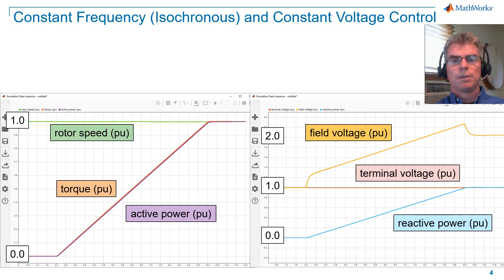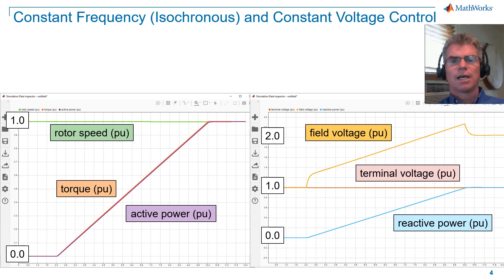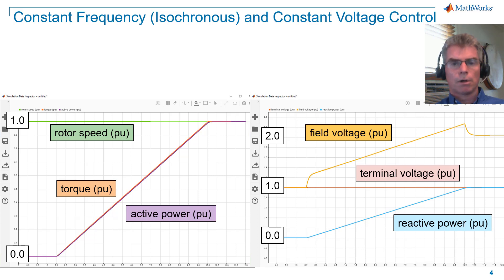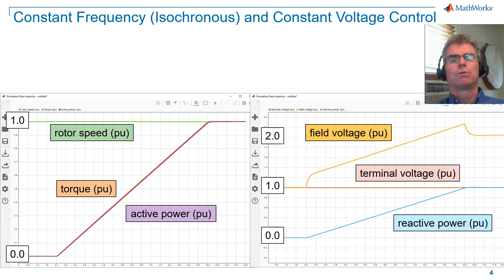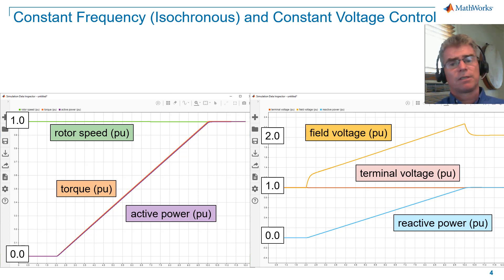Here I'm showing the result of two simulations. In the simulation on the left, I ramp up active power from zero to a nominal value of one per unit. In the simulation on the right, I ramp up reactive power from zero to a nominal value of one per unit. Note that in order to maintain a constant frequency, the speed governor increases mechanical torque, and in order to maintain a constant voltage, the AVR increases field voltage. Note that field voltage has a value of one per unit when there is no reactive power demand, and increases to beyond two per unit as reactive power increases. These results seem to suggest we have effective generator control — we have the means to regulate both voltage and frequency to constant values, which seems appropriate for effective system operation.